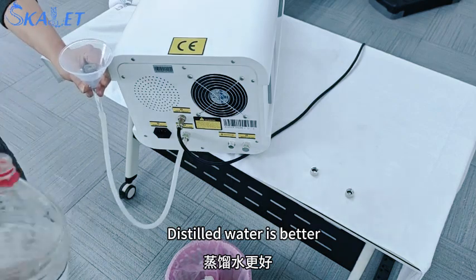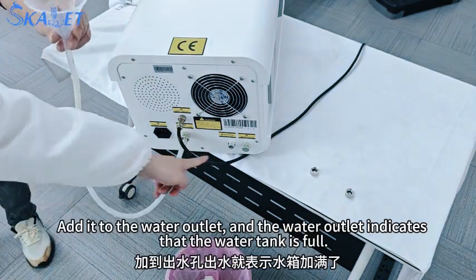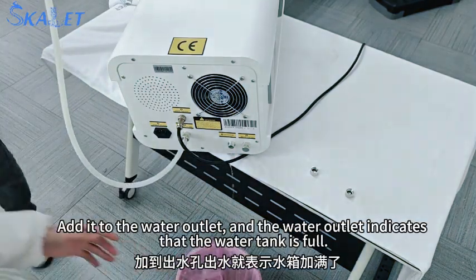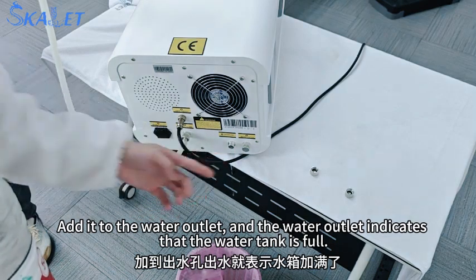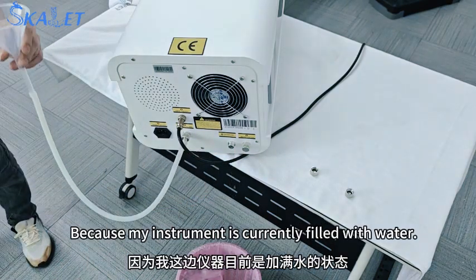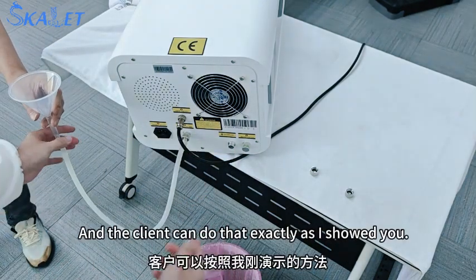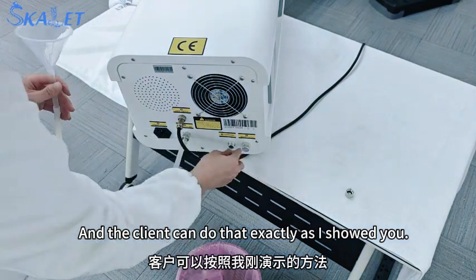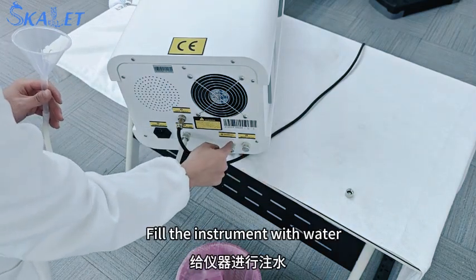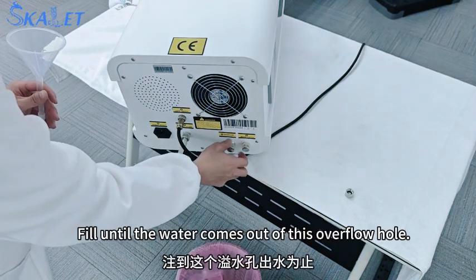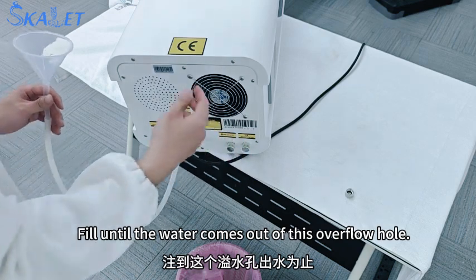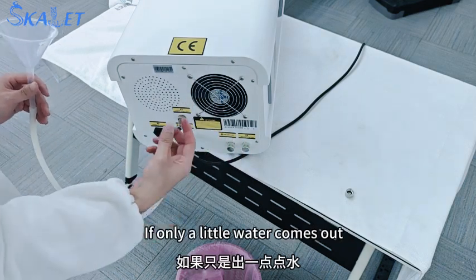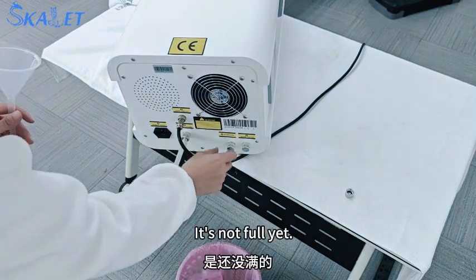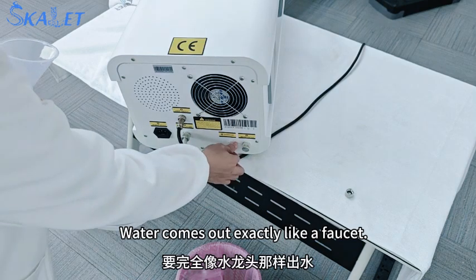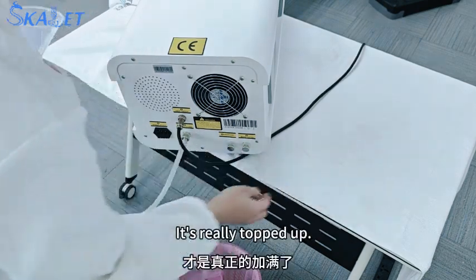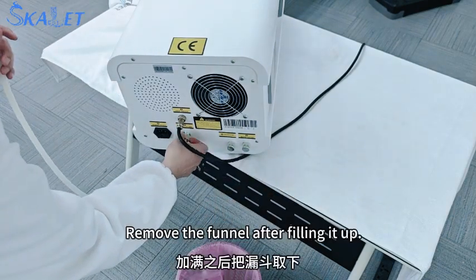Distilled water is better. Add it to the water outlet, and the water outlet indicates that the water tank is full. Because my instrument is currently filled with water, and the client can do that exactly as I showed you. Fill the instrument with water. Fill until the water comes out of this overflow hole. If only a little water comes out, it's not full yet. Water comes out exactly like a faucet. It's really topped up. Remove the funnel after filling it up.